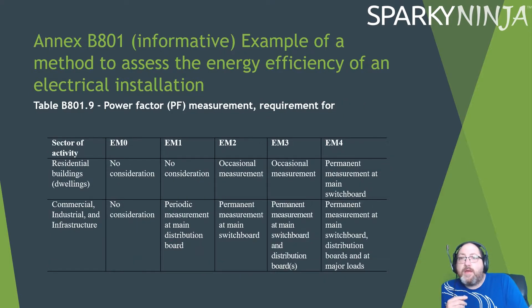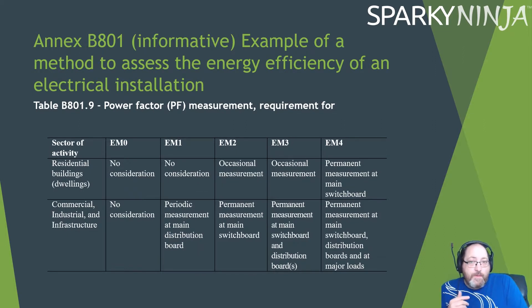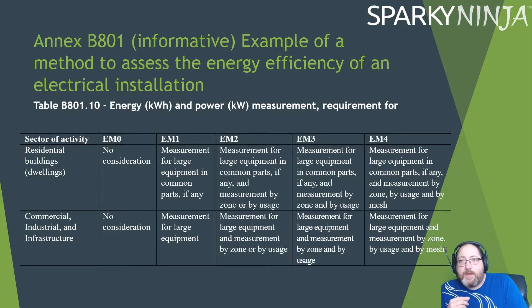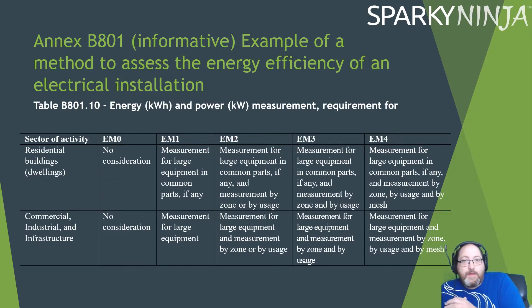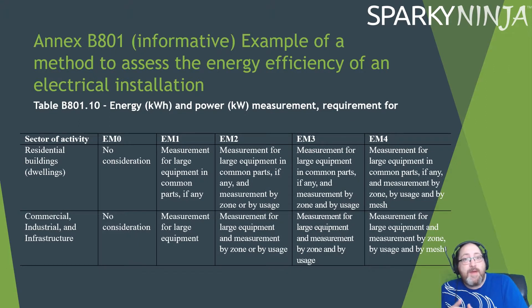For power factor measurement: permanent measurement at the main switchboard gets a four; occasional measurement gets a three or two. For energy (kWh) and power (kW) measurement: measurement of large equipment and common parts gets lower scores, while measurement by zone, by usage, and by mesh gets a four.